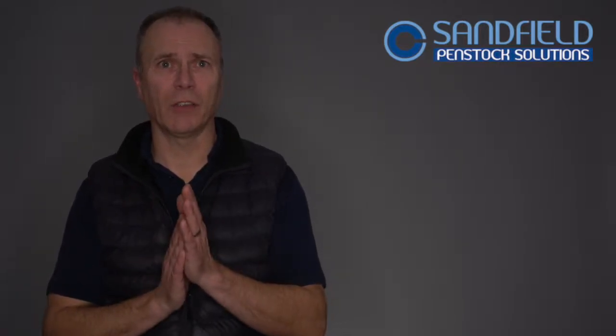What I find is that often engineers specify the dreaded word Penstock valve. This is a very generic term and probably 10 years ago was used a lot in guidance notes. You could see it everywhere. If you read things like Series 736 now, it doesn't mention the word Penstock valves. It mentions containment device, pollution containment device. Therefore, what you're looking for is a valve that actually seals. The danger is when you take the term Penstock, you're actually looking, as the English dictionary says, at a flow control device. They're different. You've got a valve that's quite slow, that was designed to stay in place for many, many years, but slow and control the flow, not necessarily isolate that flow.